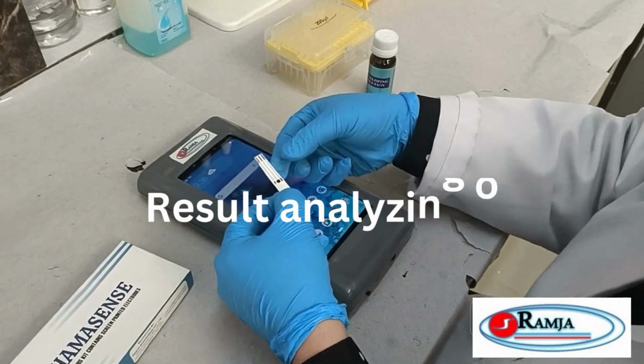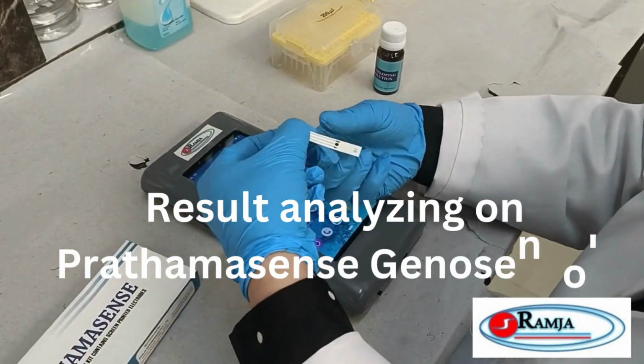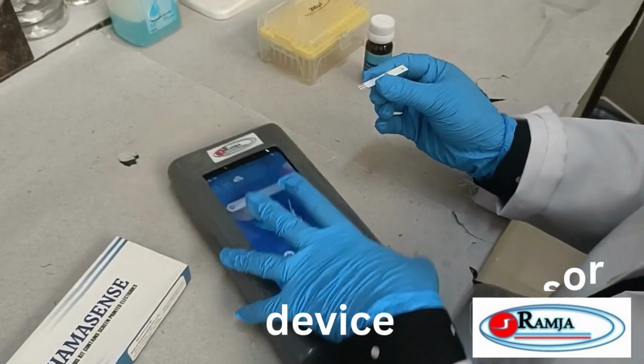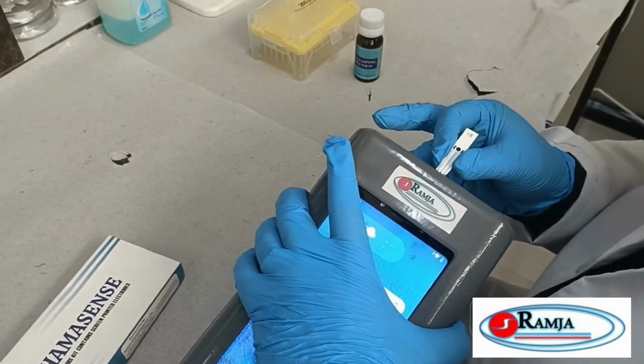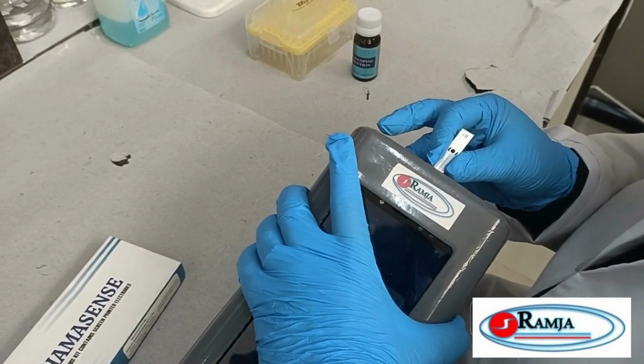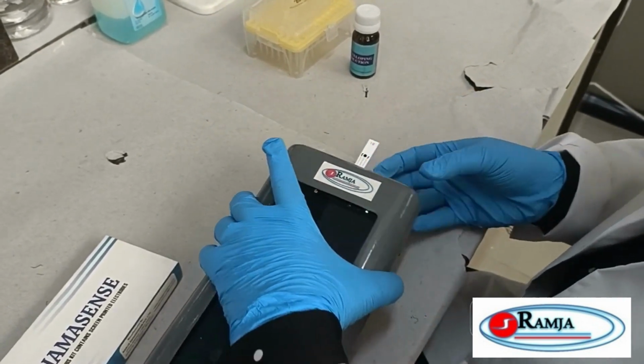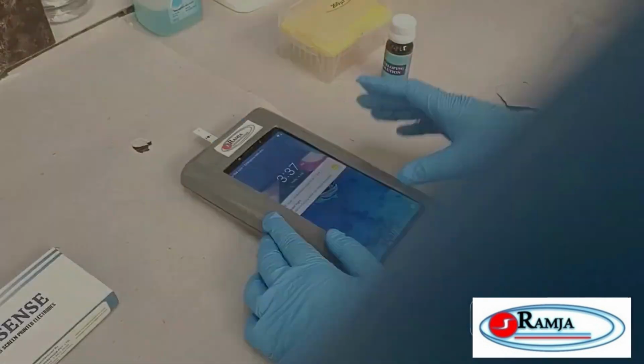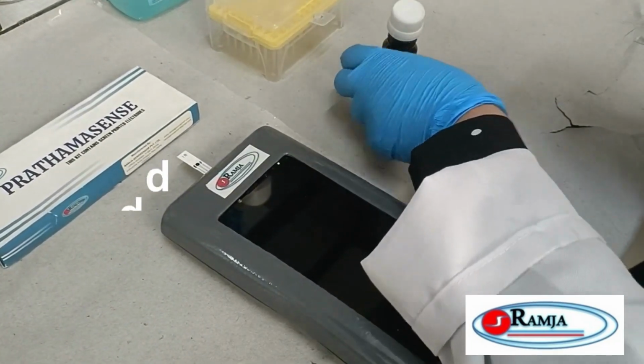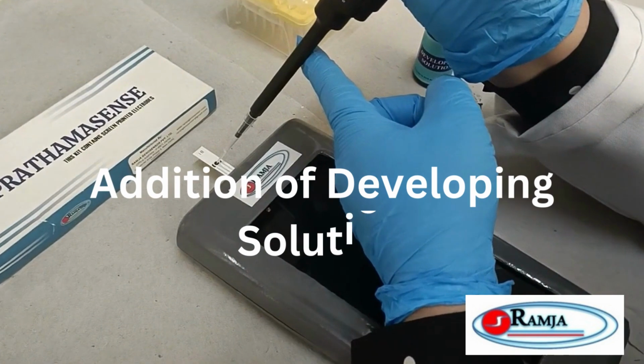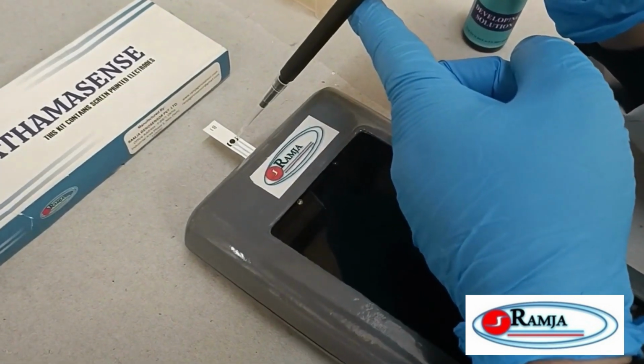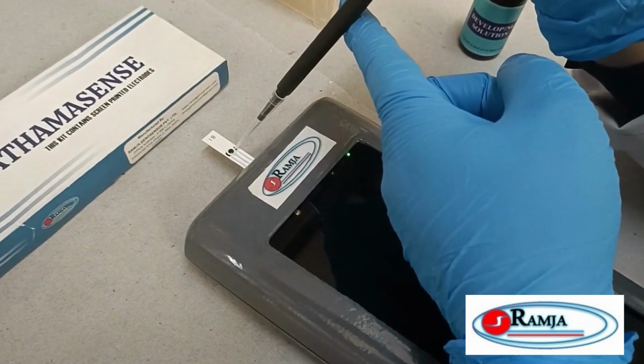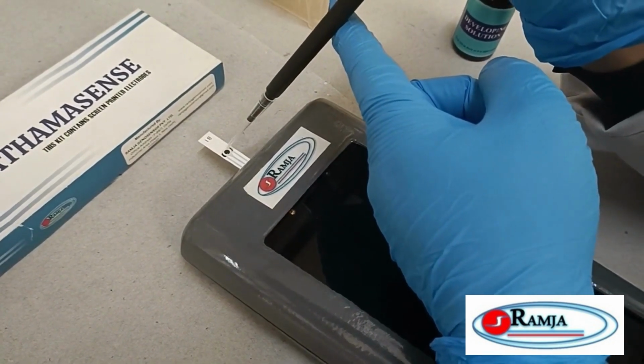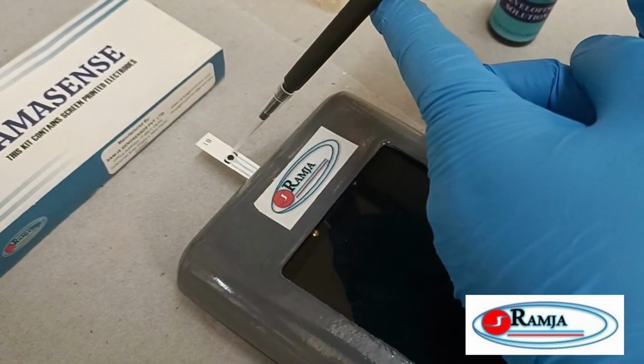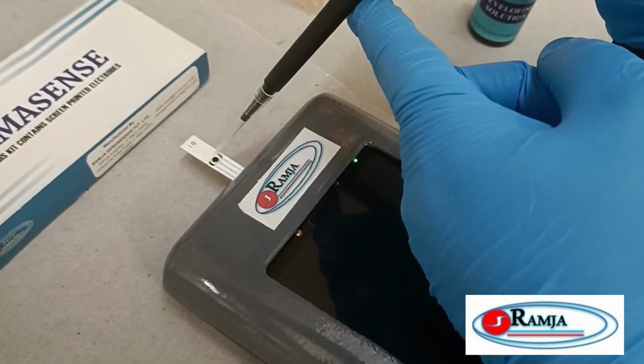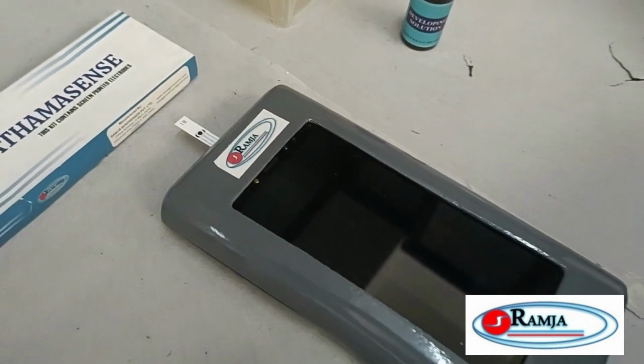So this is our processed sensor that we will analyze on the PRATHAMASENSE Genosensor device. I have inserted the sensor in the slot very carefully. Now I will add the developing solution onto the sensor surface. Make sure that the developing solution gets dispersed over the whole surface, working, reference, counter. So you have to disperse the developing solution over all the 3 electrodes.